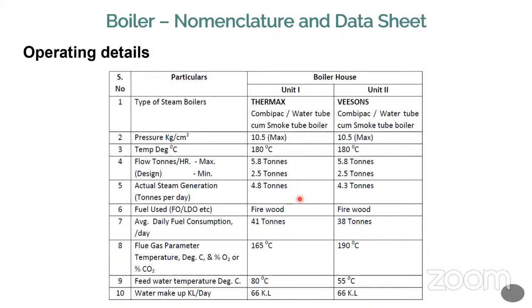Then what is the flue gas which is coming out? I told you, whenever you burn the fuel, flue gas will automatically come out. That flue gas temperature is 165, and for another boiler we have 190. But the nominal flue gas temperature is 180. So if you cross more than 180, then there is a problem. If it is lesser than 180, then there is also a problem. Okay. So around 160 to 180 is the correct value. Sometimes it may even go to 200. So 200 is slightly okay, but not correct.